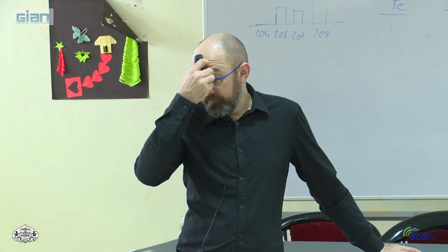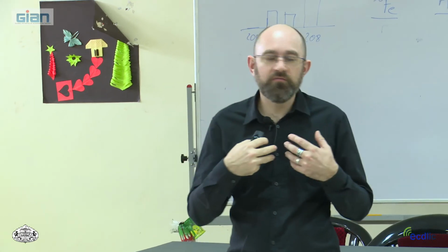Yes, because the property of the optical ICP is that there is no mass flux inside the machine, you can measure a very large range of concentration, from percent to ppm. With an ICP-MS, you can measure only very little signal, because the collectors are calibrated, are made to measure very tiny signals.